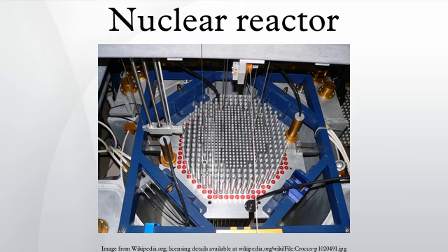Fueling of nuclear reactors. The amount of energy in the reservoir of nuclear fuel is frequently expressed in terms of full power days, which is the number of 24-hour periods a reactor is scheduled for operation at full power output for the generation of heat energy. The number of full power days in a reactor's operating cycle is related to the amount of fissile uranium-235 contained in the fuel assemblies at the beginning of the cycle. A higher percentage of U-235 in the core at the beginning of a cycle will permit the reactor to be run for a greater number of full power days.